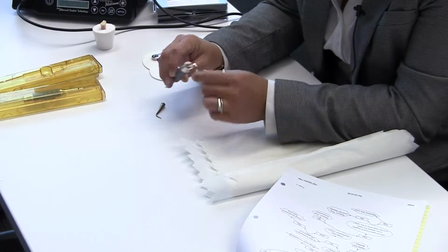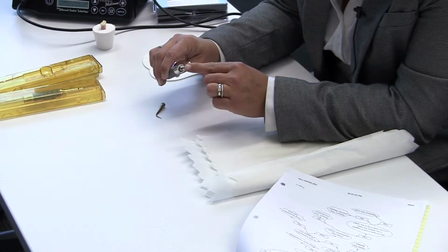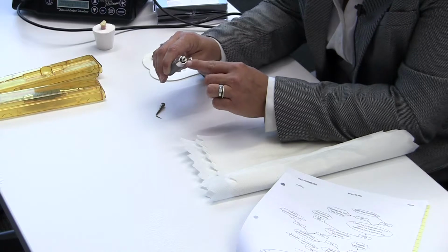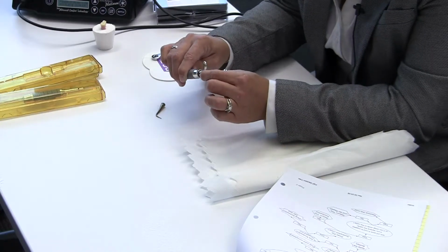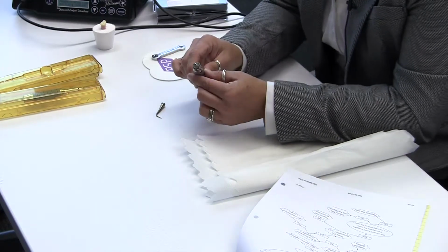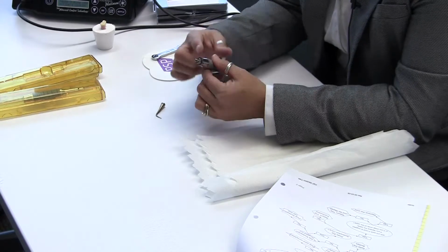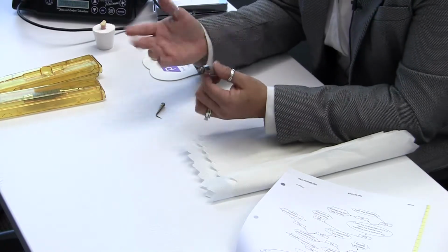Now there will always be a little bit of movement. That helps the crystals to create the vibration to actually make the unit work to remove calculus or tartar. So we are going to check the transducer and make sure that it's securely lined up and that there's equal space on all sides. If this is moving too freely, we want to make sure that we tell customer service that this is moving too freely. It renders the handpiece useless. So we're going to put this back on and move on.